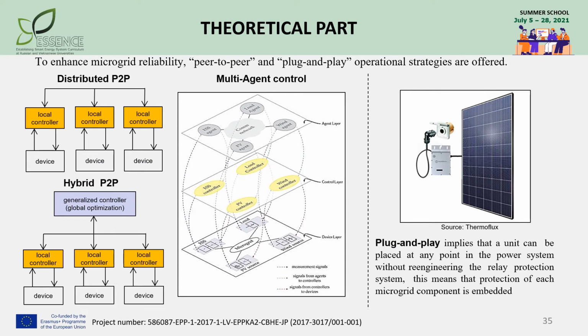To enhance microgrid reliability, peer-to-peer and plug-and-play operational strategies are offered. The peer-to-peer operational strategy ensures that there are no components, such as a master controller or central storage unit, that are critical for the operation of the microgrid. The loss of a higher level may affect efficiency but shall not influence reliability of a microgrid. A higher level generalized controller just ensures an optimal goal for all the microgrid actors. Such systems with multiple actors interacting to achieve a common control goal are called multi-agent systems, and multi-agent control strategies are a very emerging topic in the smart energy world. To allow such a control strategy, information channels shall be established between all components.